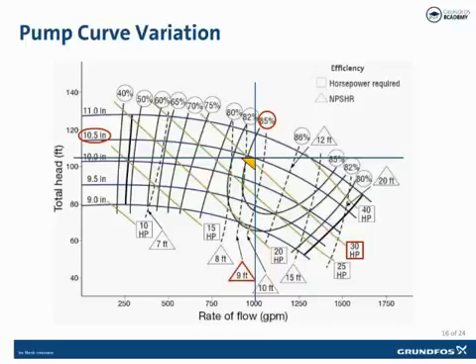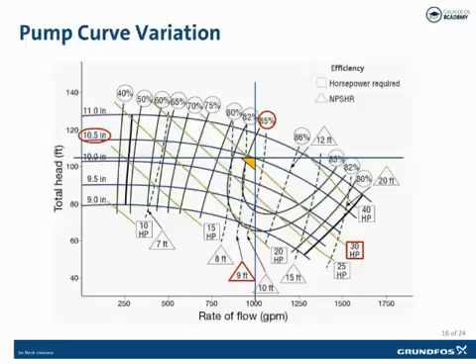At the design of 30.1 brake horsepower, a 30-horsepower motor could actually meet that requirement because it's within the motor safety factor. However, since the pump could operate beyond this design point based on actual system resistance, we must select a motor that can operate anywhere on the pump impeller curve. In this case, the pump can easily surpass the 30-horsepower capability of the motor, so a 40-horsepower NOL — non-overloading — motor would be selected.